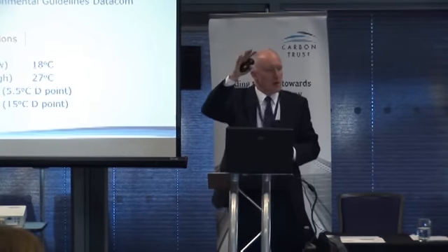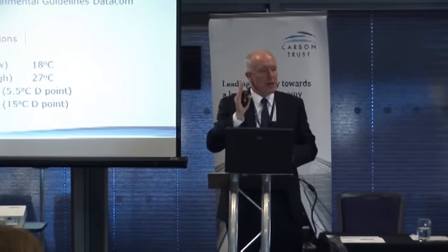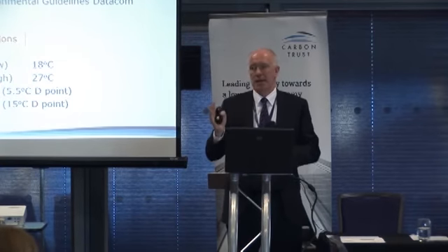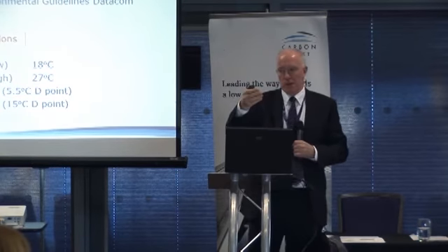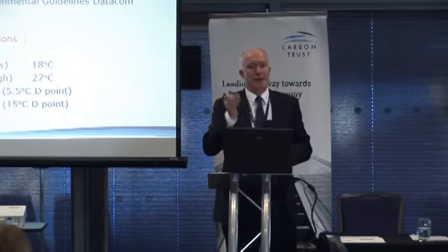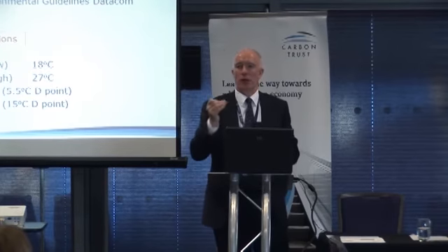What are we talking about? If you've got a network server and we want to keep it in a controlled temperature, we are not concerned about anything else than the air inlet temperature. So you've got a box where the transistors may get to 70, 80 degrees centigrade, and what we need to cool that is stable air on temperature. That's the cold air going onto the unit.